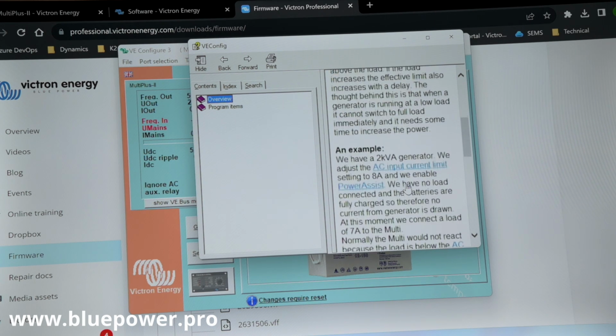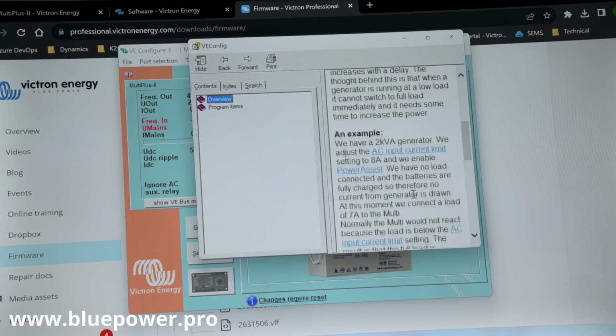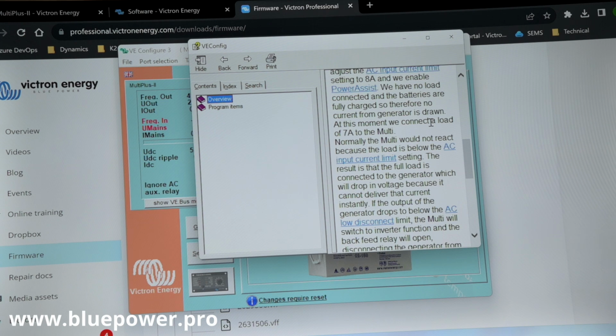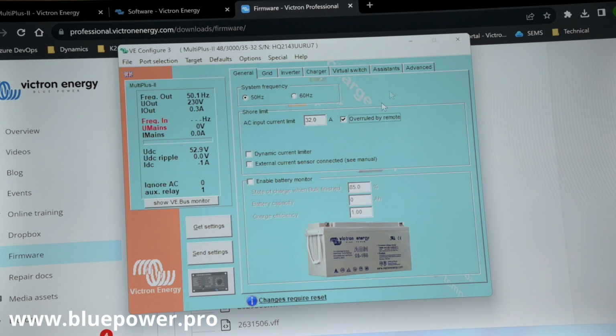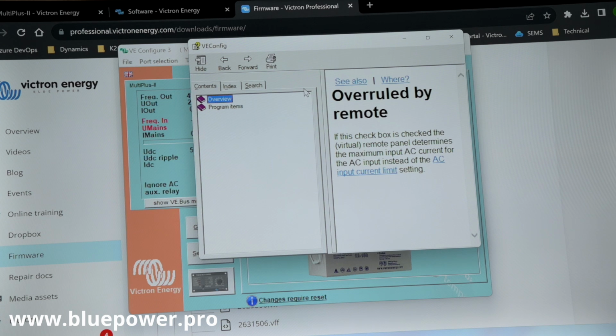Specifically, they've got it set for a small generator like a 2 kVA. Instead of running 32 amps from your generator, which can only supply 6, it's going to ramp up 1 amp, 2 amps, 3 amps up until 6 amps, and it's going to try 7 and 8, and see, oh no, the supply can't keep up. I'm only going to draw 6 amps because my supply can only steadily supply 6 amps. That's what the dynamic current limiter does. Limited generators can activate that. Then there's the external current sensor, if you've got a unit with one. Any setting you want to see what it does, you can just right click on it and it will tell you exactly what that setting does.